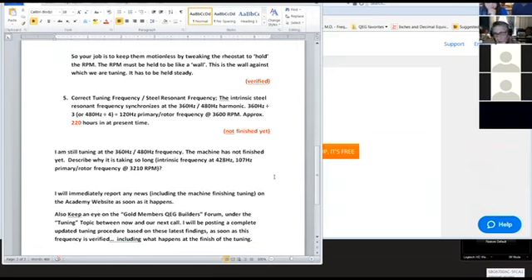So I guess what I'd like to do, if somebody could try this out, is, the only way that I'm pretty sure that this is going to finish, I'm sure it's going to finish at 120 hertz. It just has to take the time because it's doing two things: pushing out the other frequency and embedding the new frequency at the same time. But I would like, if one of you guys, the machine, could run it according to the previous instructions, but at 428 hertz, which is 107 hertz on the primary, and it would be 3210 RPM.